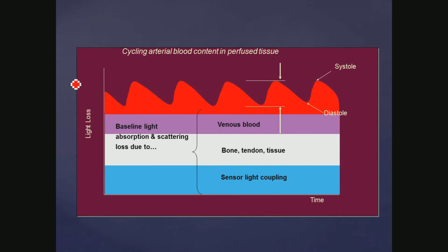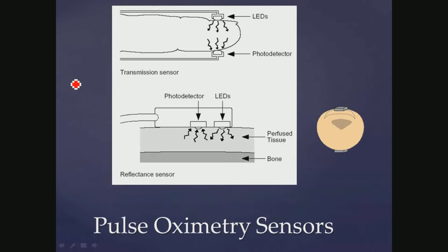And again, the sensors are designed, the typical one we use is the one on top, the transmission sensor, where LEDs are emitting light and detecting it on the opposite side. There is technology that is a reflectance sensor, and I'll show you some examples of those and what some problems can exist. Most specifications are one standard deviation, as far as ±2 for adults, or ±3, with a range of 70 to 100%.